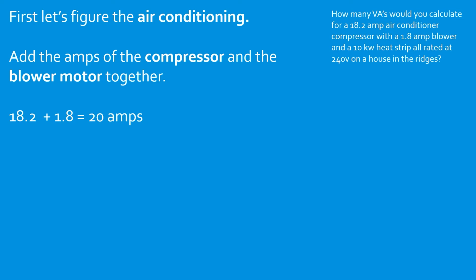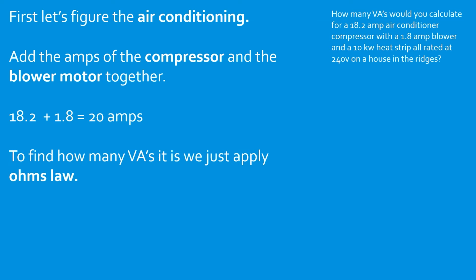Now we need to convert that over to VAs. In order to do that, we're just going to apply Ohm's law like we've learned. So we take our 20 amps and we multiply it by 240 volts, because it was stated in our question that they're all rated at 240 volts, and that's going to give us 4,800 VAs or 4.8 kVA. Now we can set that to the side and we'll calculate the heat.